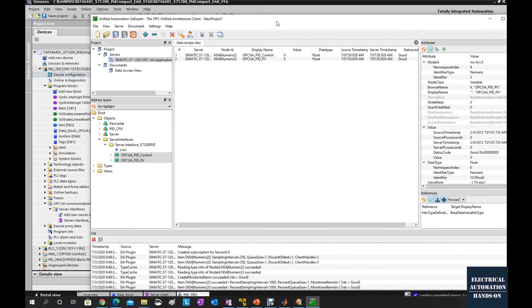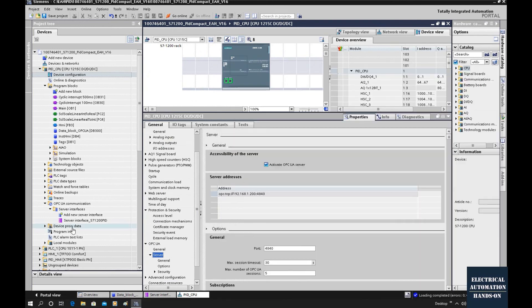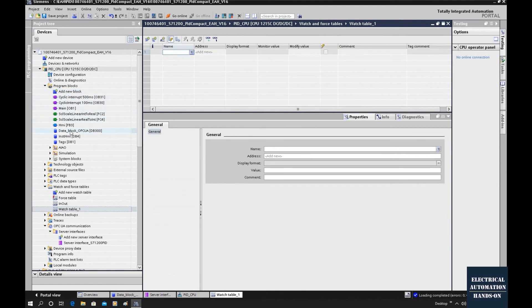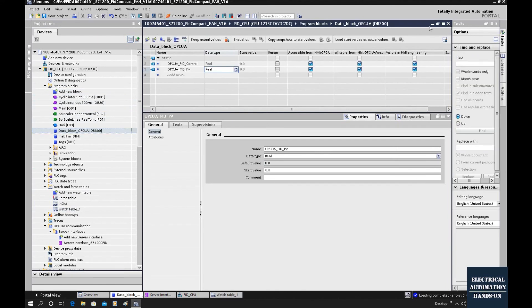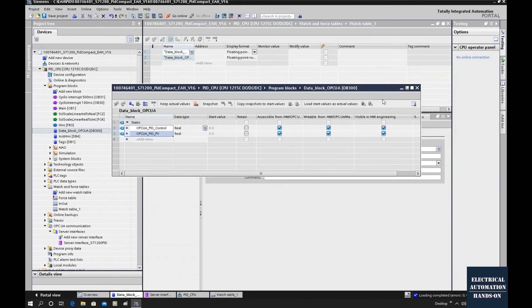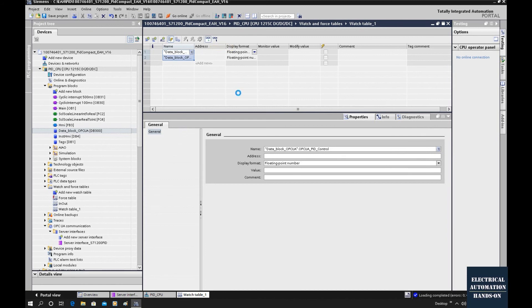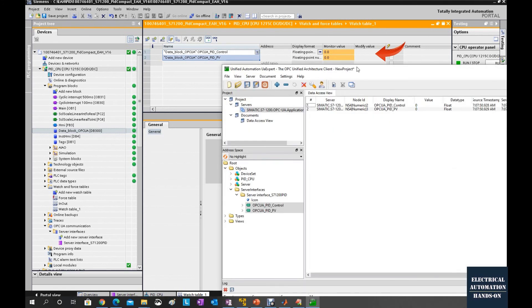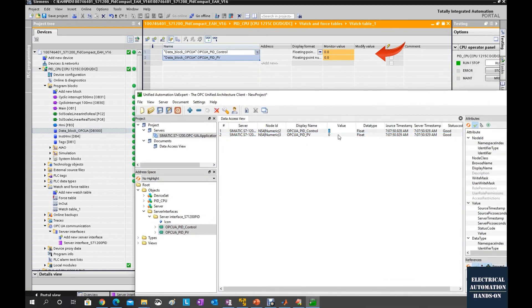Let's test the data. From the PLC side, we can create one watch table, then open the data block OPC UA and drag the two tags into this table. Keep the monitor running — the system will go online and monitor the actual values of these two tags, currently both zero. From the UA Expert client, let me type in some data — let's set 20 and 30.